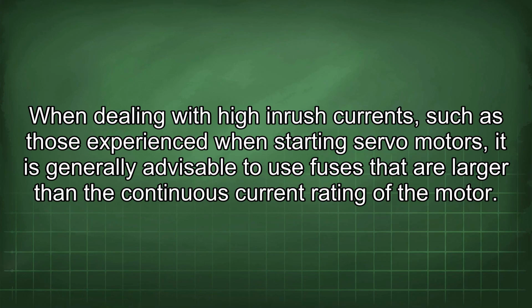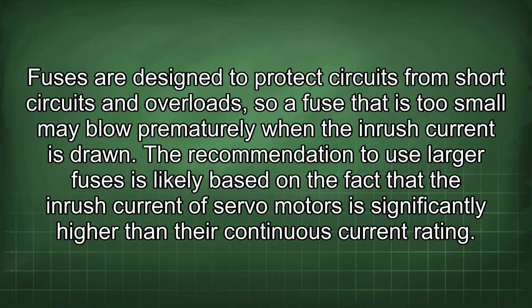When dealing with high inrush currents, such as those experienced when starting servo motors, it is generally advisable to use fuses that are larger than the continuous current rating of the motor. Fuses are designed to protect circuits from short circuits and overloads, so a fuse that is too small may blow prematurely when the inrush current is drawn.